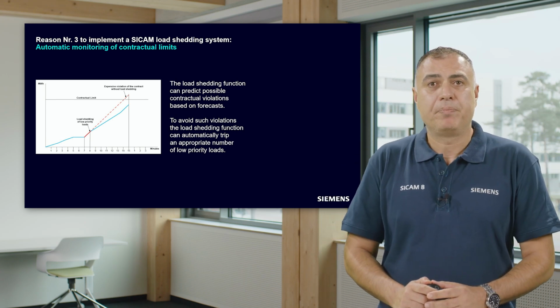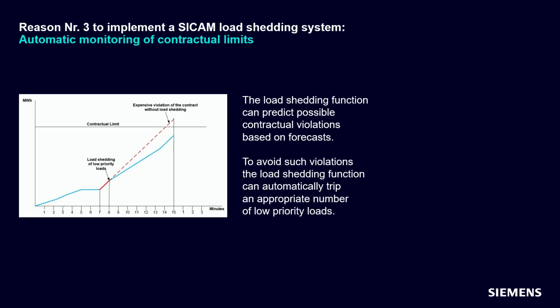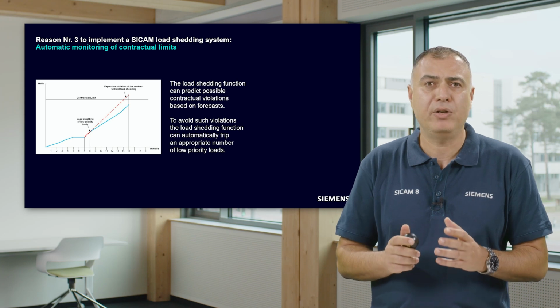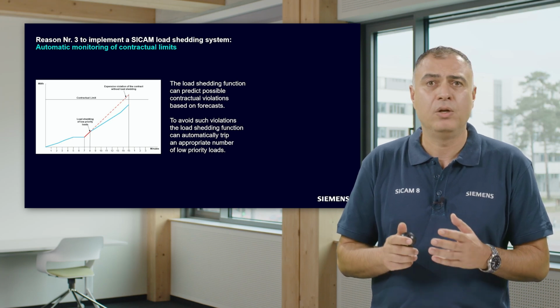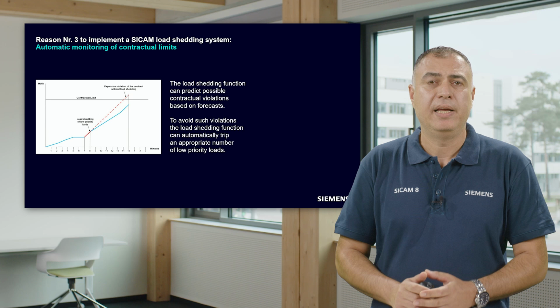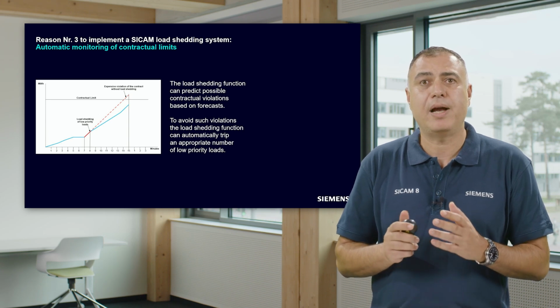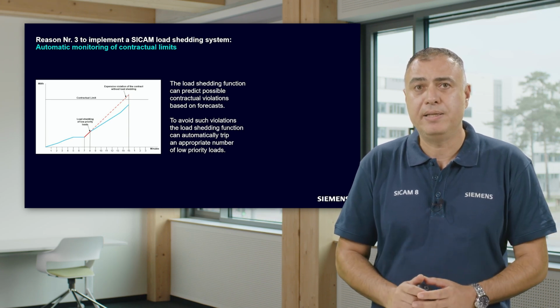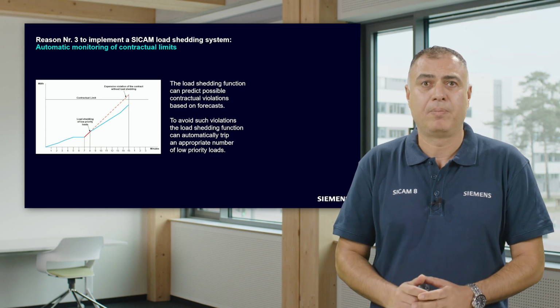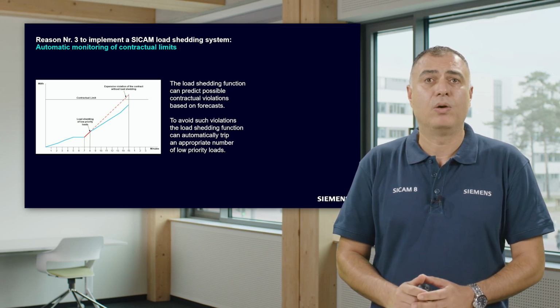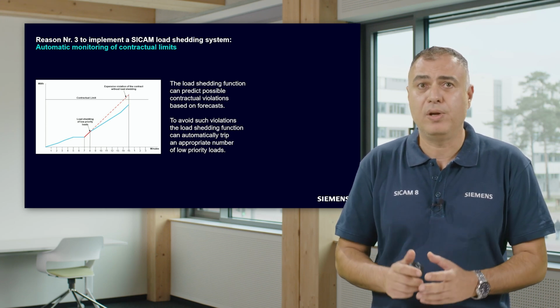Reason number three is a more sophisticated use case. Usually, the energy consumption of an industrial plant from the public grid is limited by contracts. It is a common practice to monitor the consumption in time periods of 15, 30, or 60 minutes. If a plant exceeds the contractual limit, high penalties may be accrued. A load shedding system can also monitor such contractual limits.